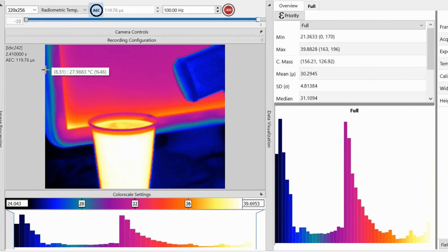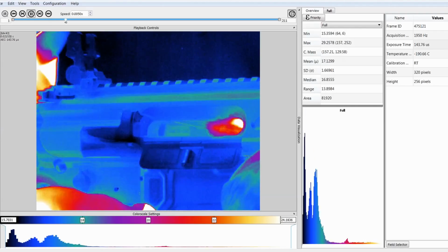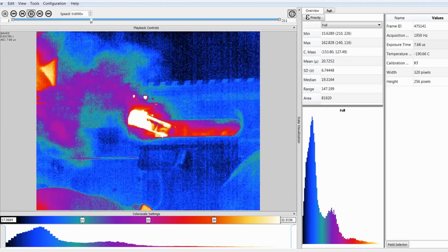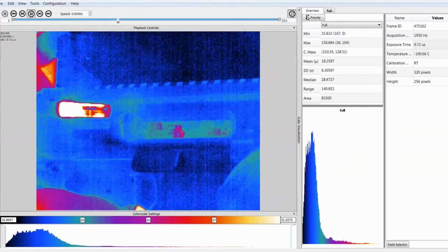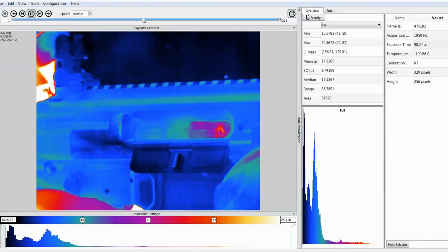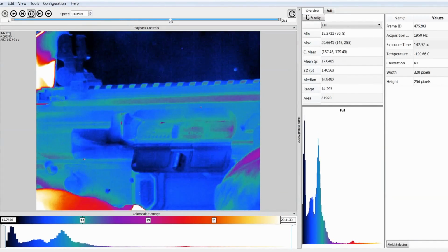So the exposure time flexibility that's inherent to the Telops calibration allows us to offer some unique operating modes, including what we call automatic exposure control. This feature allows the camera to read in the scene radiance and autonomously adjust the exposure time to maximize the signal-to-noise ratio or to prevent saturation.